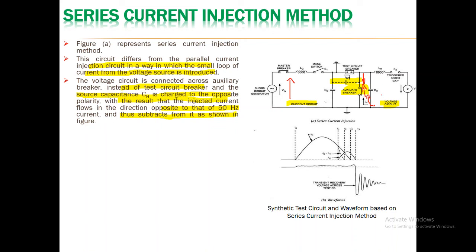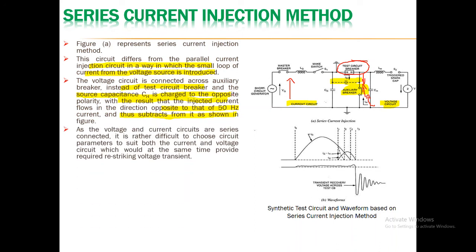Both currents are in opposite directions and will subtract from each other, as seen in the figure across the auxiliary breaker. The test breaker is connected in series between the current circuit and the voltage circuit, whereas in the parallel injection method the circuit breaker under test is connected across both circuits. In the series current injection method, the currents at the auxiliary breaker cancel each other out. Since the voltage and current circuits are in series through the breaker, it is rather difficult to choose circuit parameters to suit both simultaneously while providing the required restriking voltage transient.